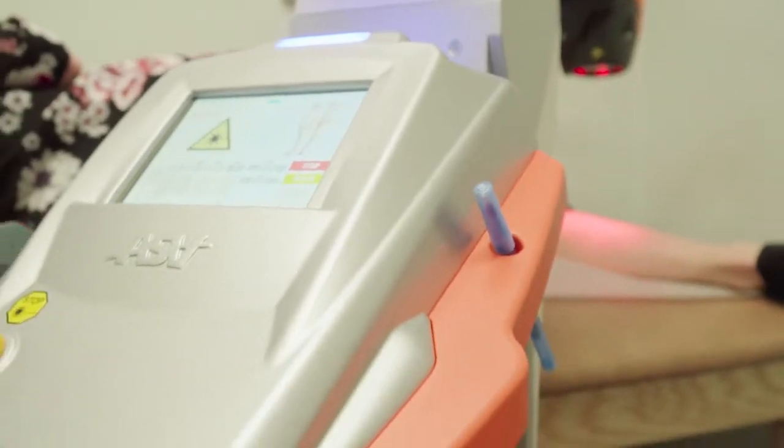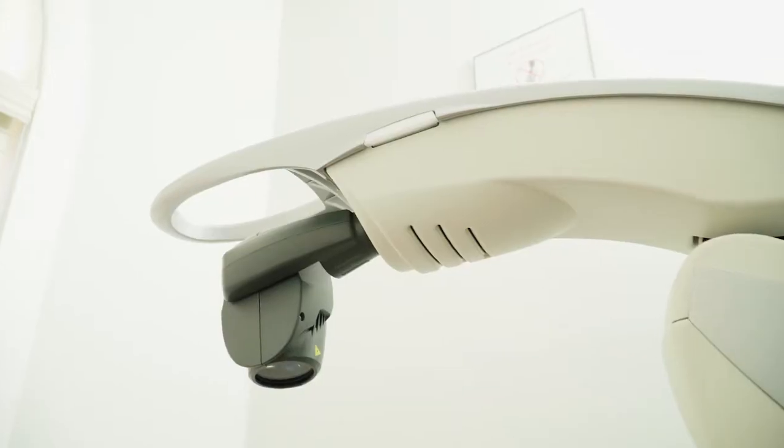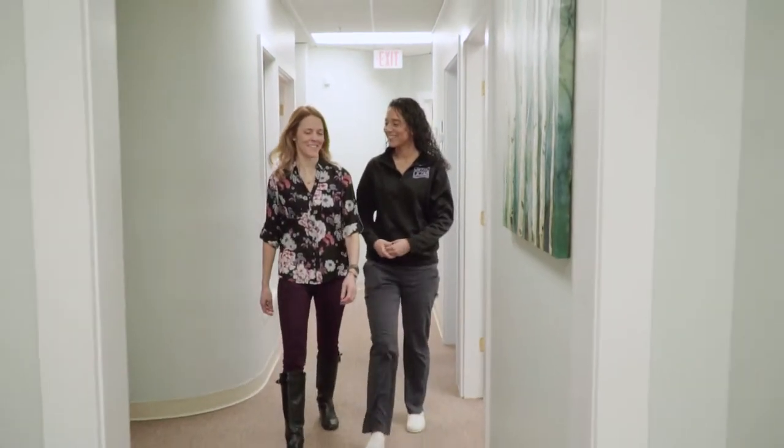What's also really important with laser — especially a class 4 laser — is that when you talk about classes of laser, it really means about the power of the laser. The peak power of the M8 laser is 75 watts, which puts it into a class 4 category. There are other class 4 lasers out there, however they deliver a continuous amount of energy, which means there's concern for tissue heat energy getting too high. So they have to be handheld, kept moving into the zone of where the inflammation is. They can provide pain relief with those correct wavelengths, but they require a technician to hold the wand throughout the entire treatment.